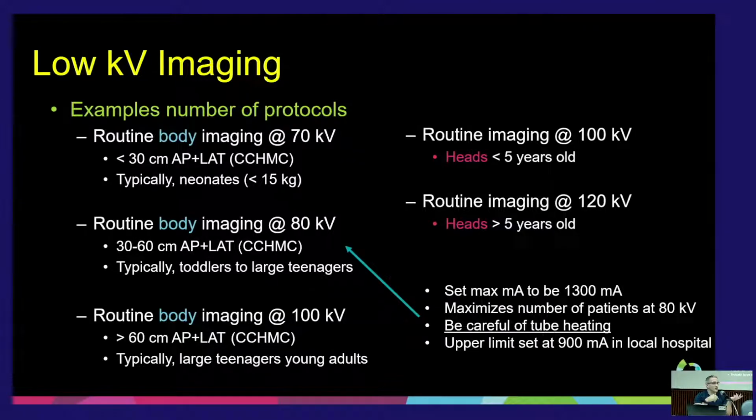And so if the radiologists need to look at fine detail in the bones, it's harder. We've had some of our radiologists complain about the 70 kV images, saying the bones looked translucent. They just don't look right. And it's because 70 kV just absorbs all those photons. So there's not a lot of detail in the bone. And so for us, our radiologists love 80 kV. And so imaging at 80 kV when you're doing, say, a CTA, so then there's iodine on board, those images just look beautiful. I mean, our doctors love our CTAs on our system when we image at 80 kV.